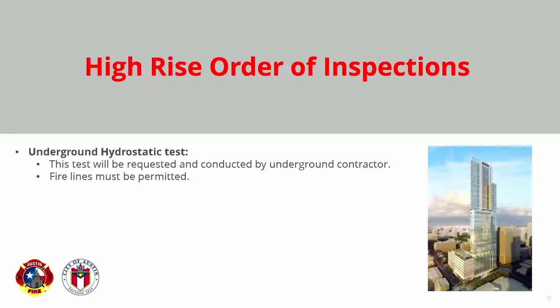This particular one, the underground hydrostatic test, doesn't have to be done first, but the sprinkler company will appreciate it if it does get done first, because they can use the water from the city to fill their pipes for their hydrostatic tests while the building's being built. It takes a long time to fill them with a garden hose, so underground hydro is something you want to get taken care of very soon. It consists of a 200 PSI test from the valve at the street to the stub end of the building.